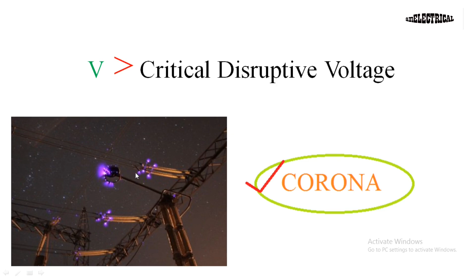This case is practically not possible because the distance is fixed in case of a particular voltage transmission line. It's a matter of construction, so we cannot change this distance at any time. So practically what happens is, generally the voltage becomes higher, which is the second case. However, when the applied voltage exceeds a certain value called the critical disruptive voltage, then only the faint violet glow appears surrounding the conductor, called corona.